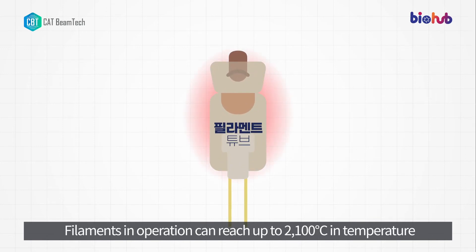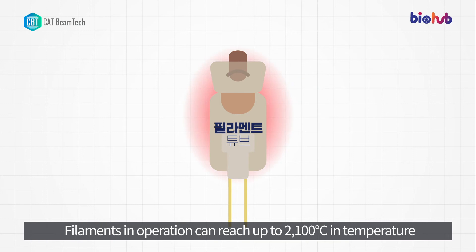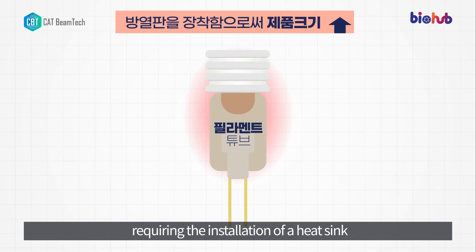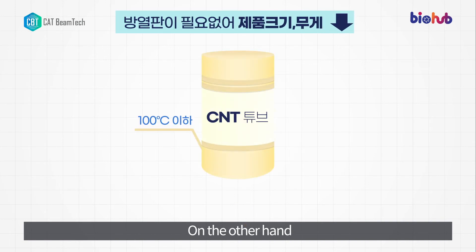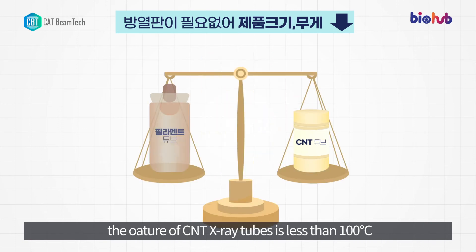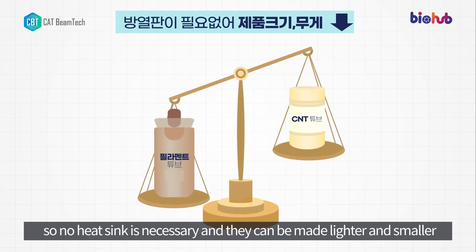The last benefit is miniaturization. Filaments in operation can reach up to 2,100 degrees Celsius in temperature, requiring the installation of a heat sink. On the other hand, the operating temperature of CNT X-ray tubes is less than 100 degrees Celsius, so no heat sink is necessary and they can be made lighter and smaller.